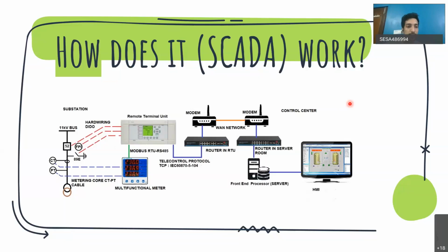To simplify things, I have shown your substation equipment here on the left. In general, you have distribution substations with power transformers stepping down from 66 kV, 33 kV, etc. to 11 kV, and from the 11 kV bus, individual 11 kV feeders emanate outside.